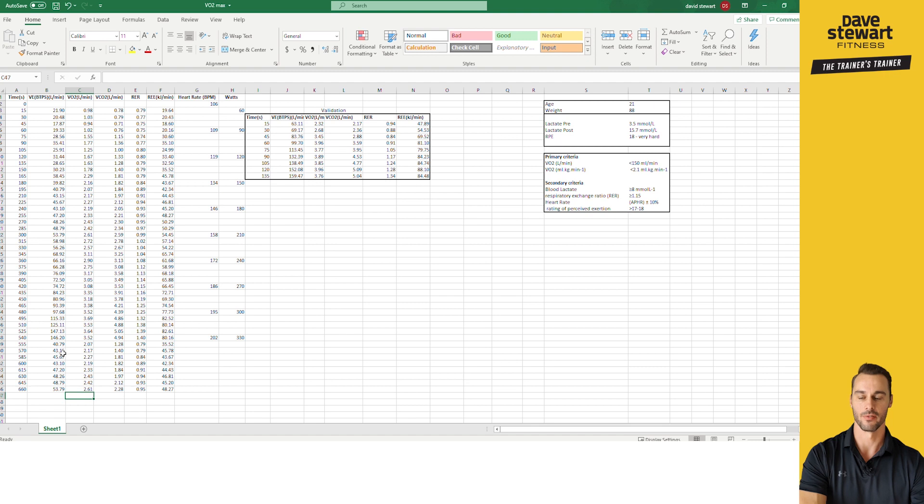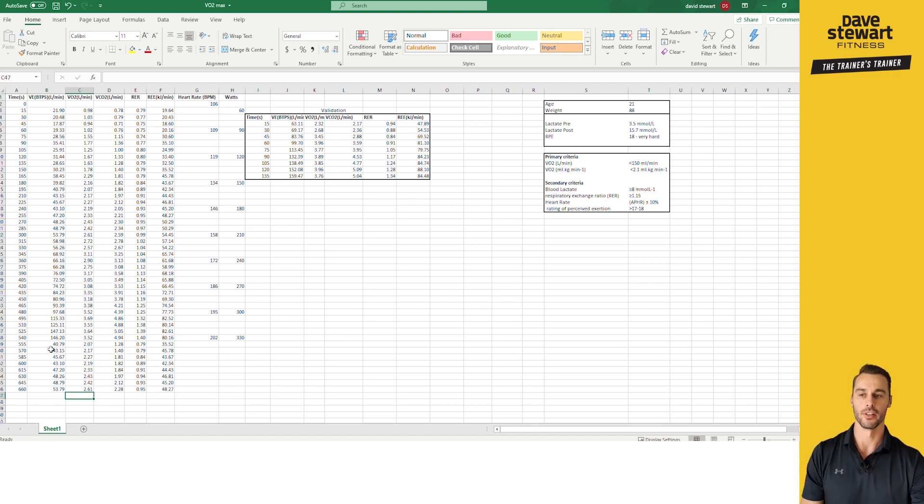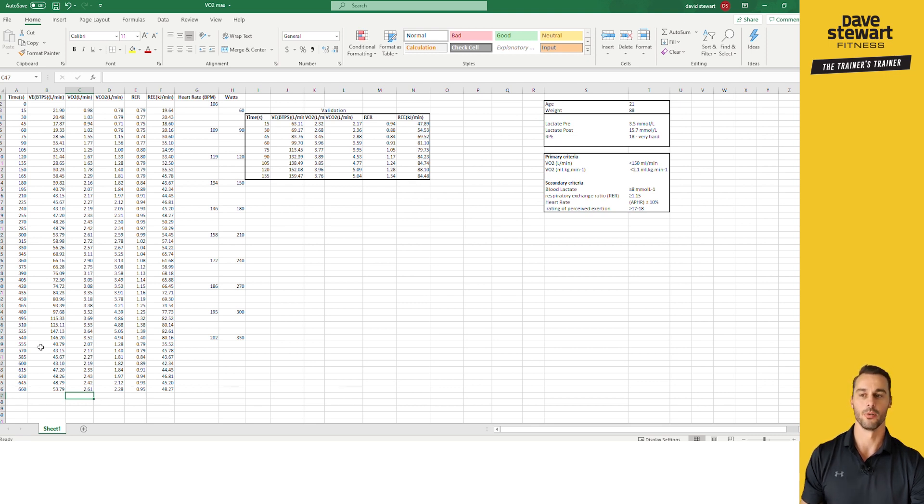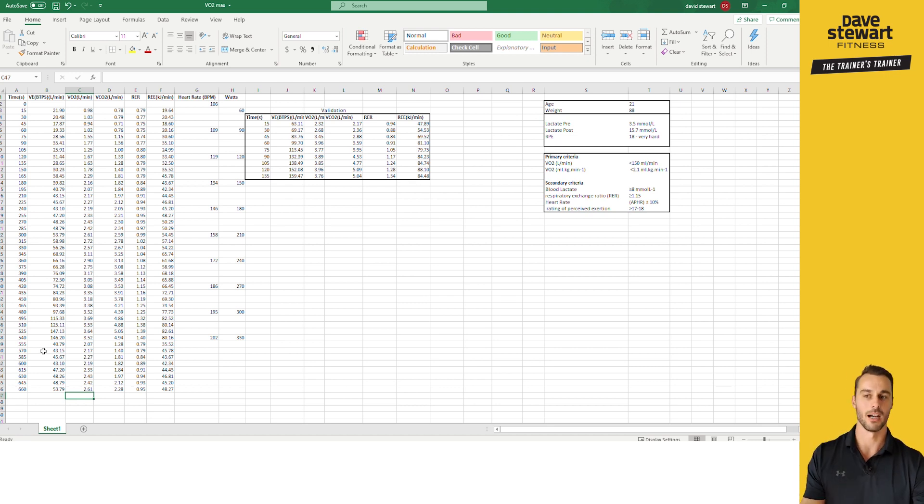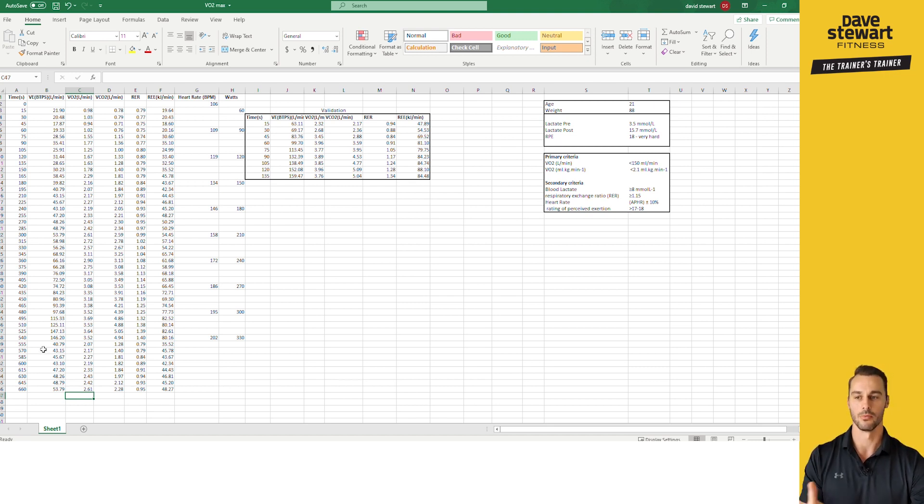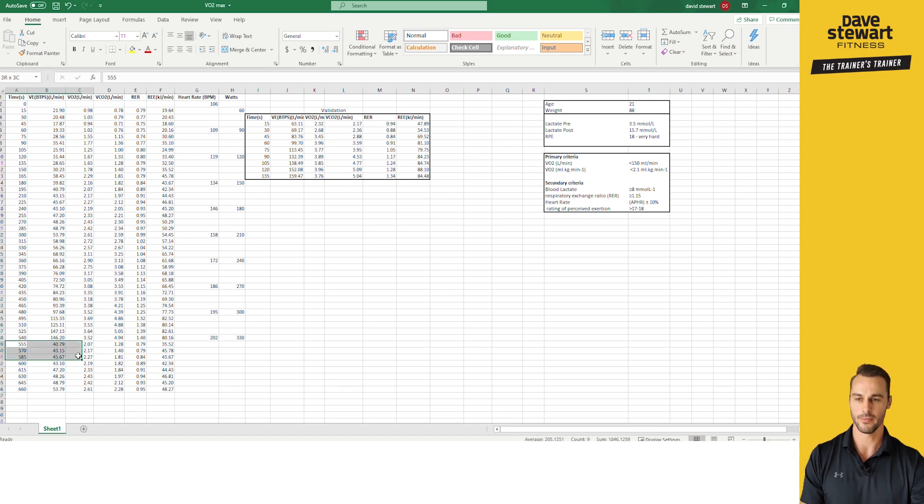So I just cut and copied this in. This actually isn't from the test, but this is what you have to be wary of, that you can't just grab any data at the end there because there may be a couple of data points that are invalid or they've actually taken the mask off and it's still analyzing. So from there to there, that stuff's no good. So I can just delete that for now.